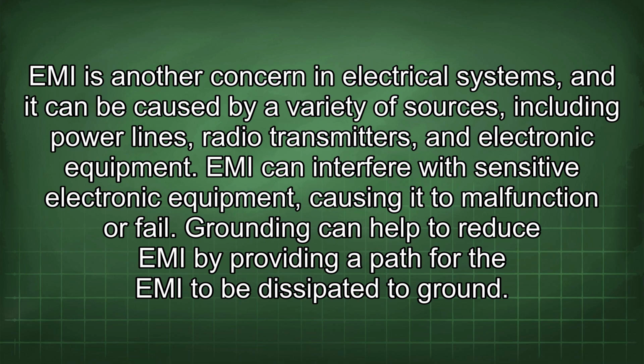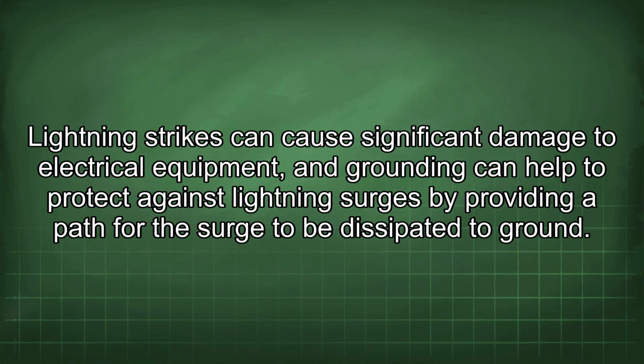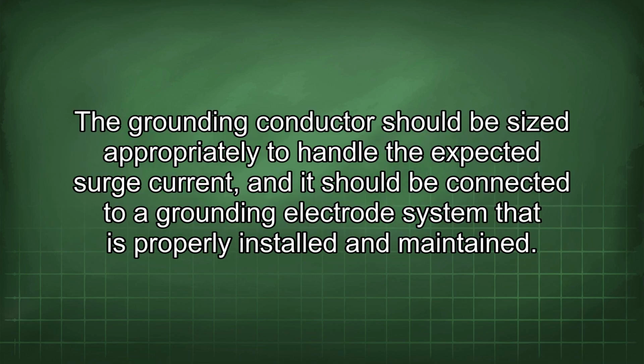EMI is another concern in electrical systems, and it can be caused by a variety of sources, including power lines, radio transmitters, and electronic equipment. EMI can interfere with sensitive electronic equipment, causing it to malfunction or fail. Grounding can help to reduce EMI by providing a path for the EMI to be dissipated to ground. Lightning strikes can cause significant damage to electrical equipment, and grounding can help to protect against lightning surges by providing a path for the surge to be dissipated to ground. The grounding conductor should be sized appropriately to handle the expected surge current, and it should be connected to a grounding electrode system that is properly installed and maintained.